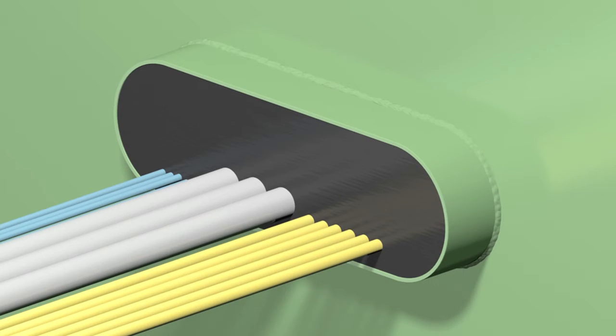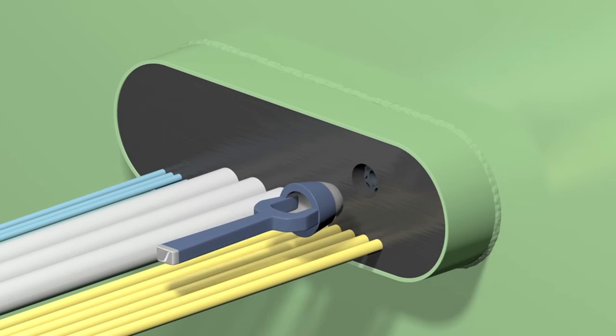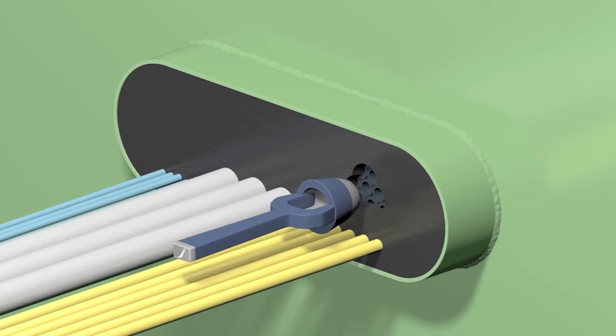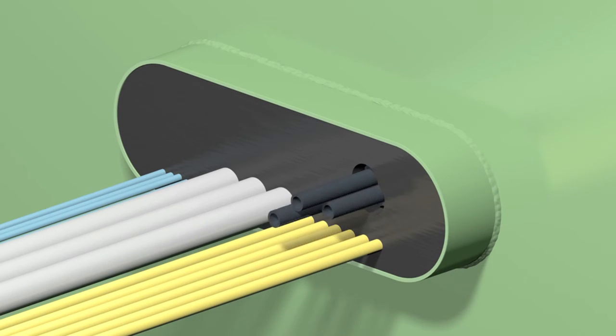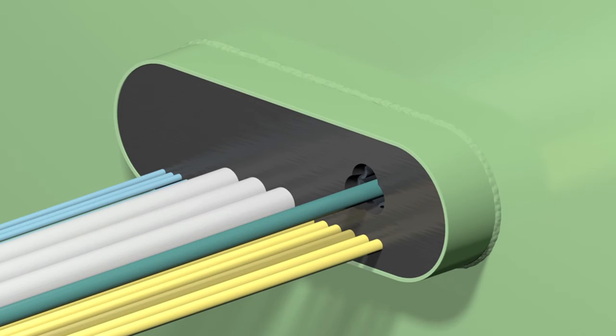Adding extra cables through a finished rise multi-cable transit is an easy job. Cut away the sealant layer at both sides of the penetration with a plastic knife or a hollow punch in a tapering shape at a spot where there is sufficient free space. Remove one or more filler sleeves to create an opening for the cable to be ducted. The opening should be large enough for the cable with an insert sleeve around it. The cable is pulled through the free opening in the rise multi-cable transit. Place a rise sleeve around the cable and push it into the conduit. Add extra single sleeves to fill any open spaces.